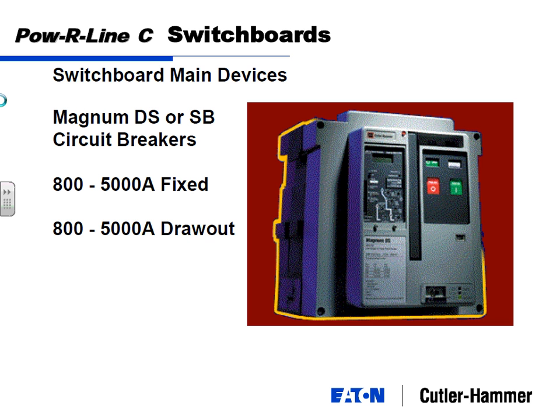Switchgear feeding a switchboard, for example, as a load. A switchgear breaker would use a Magnum DS. The Magnum DS breaker is tested to withstand 30 cycles. Harkening back to the early slides about the withstand, it can sit there and let the full fault current flow through it while it delays, while it looks downstream, and that lets something downstream be the one that trips.